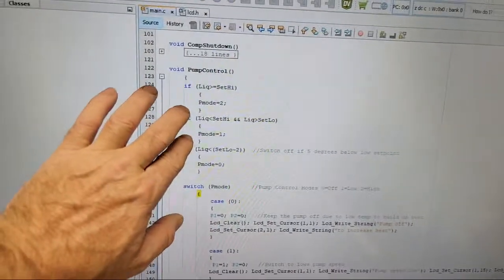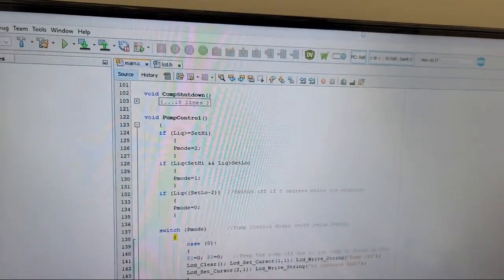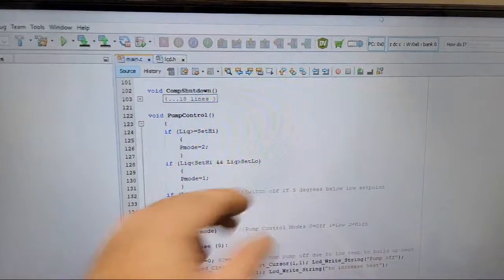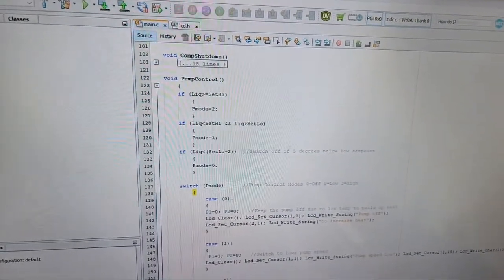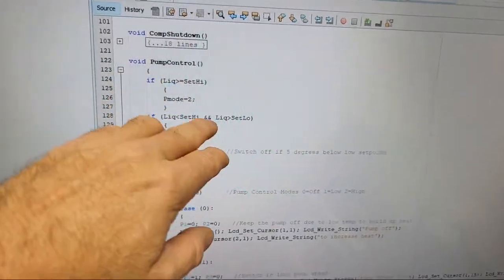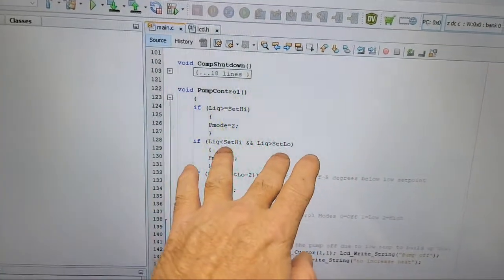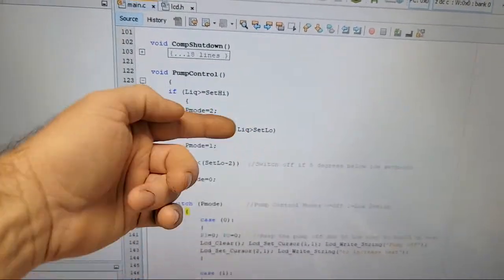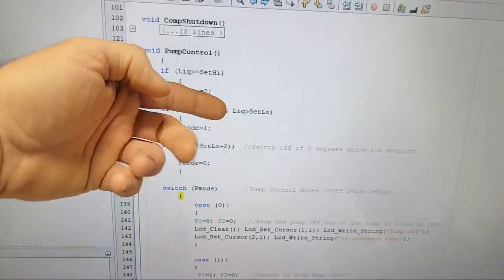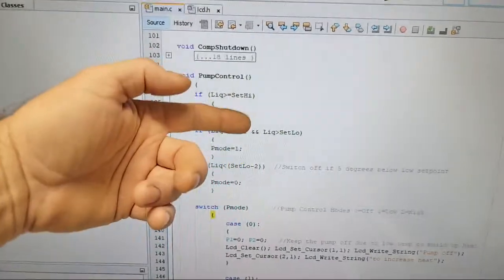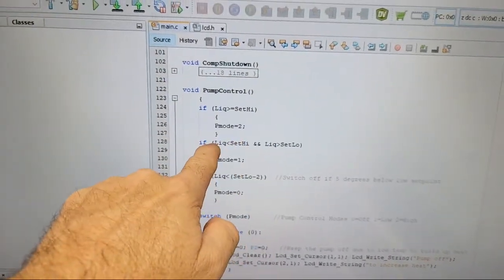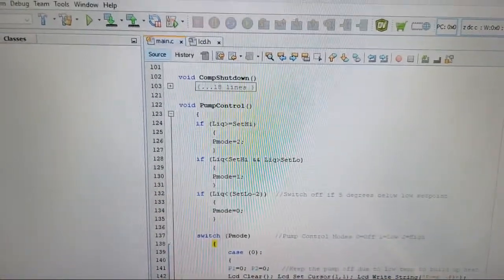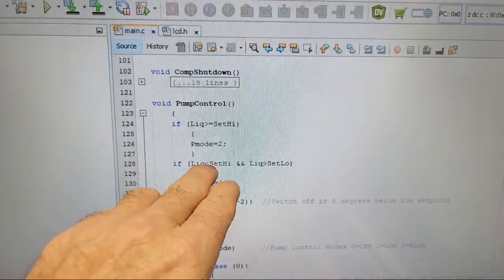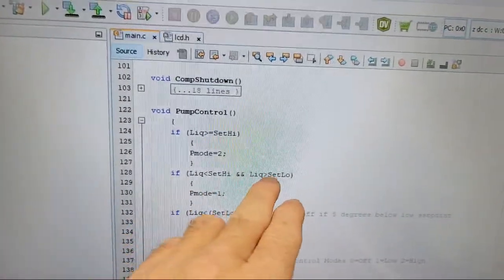But in this condition right here, it is P mode one. So if this liquid line is less than set high and liquid line is greater than set low—the reason you have this statement is because when the temperature is above set low, it's going to go to P mode 1. But if the temperature is way high, it would still meet that condition. But you want it to where the temperature reaches the next threshold set point, the second set point, so this is no longer viable, because the liquid line has to be less than the high set point, but above the low set point.